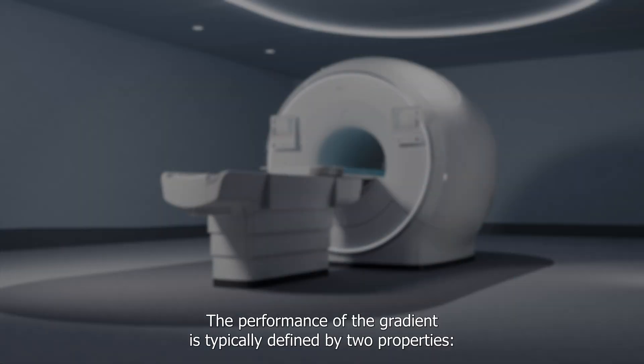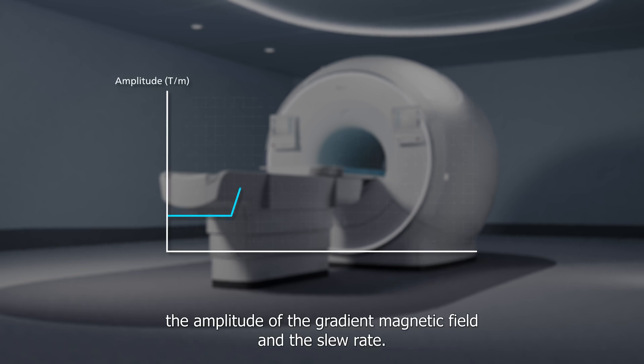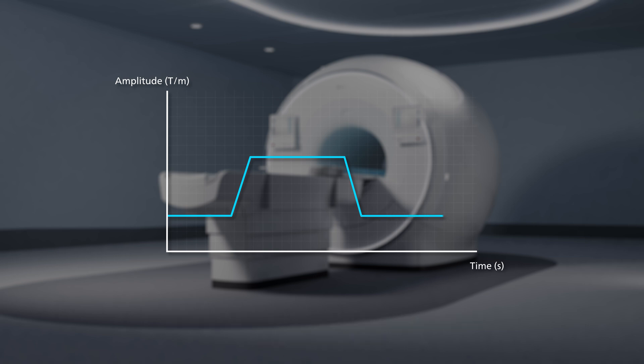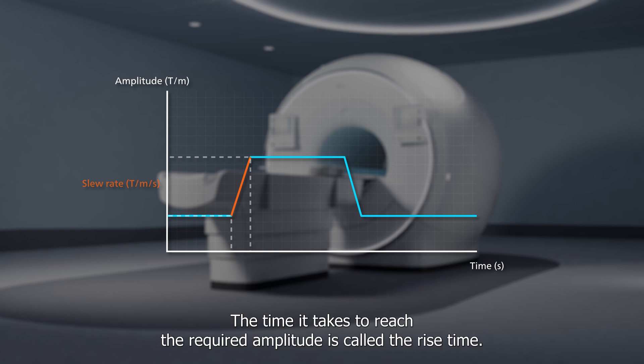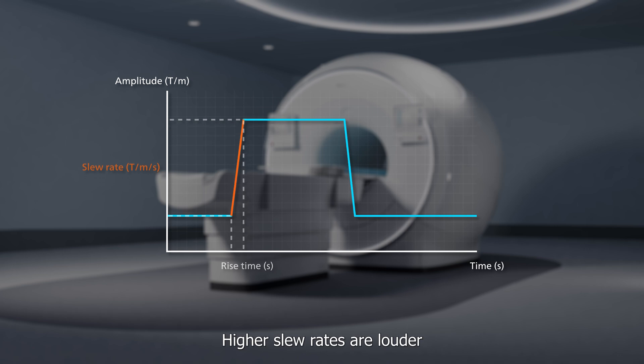The performance of the gradients is typically defined by two properties: the amplitude of the gradient magnetic field and the slew rate. The slew rate is the speed at which the gradients can reach the required amplitude. The time it takes to reach the required amplitude is called the rise time. Higher slew rates are louder.